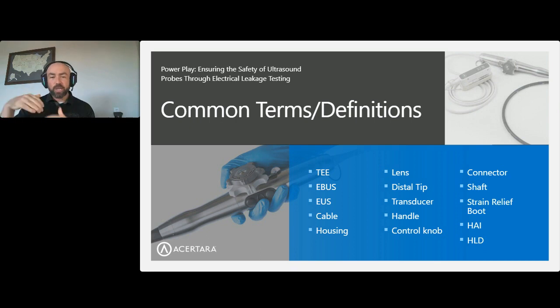That electrical signal changes the shape or vibrates the crystal in the end of the ultrasound transducer. And as that crystal changes shape, it produces pressure waves, right? Sound. And that sound will travel into the body. It gets absorbed, it gets reflected, it gets attenuated as it is moving through the body. And each time reflections are sent back through a period of time, those are received by that same crystal and reinterpreted. The pressure waves come back, and they actually compress that crystal again.